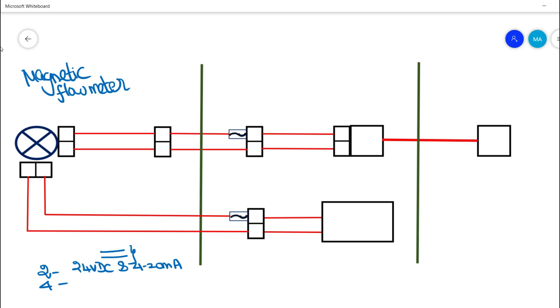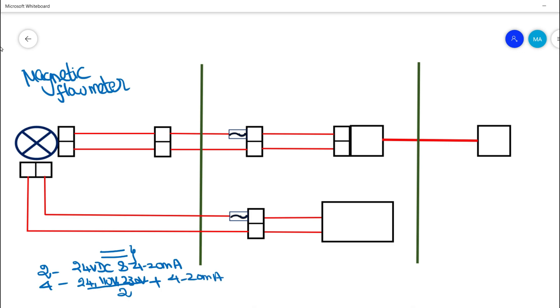In 4-wire systems we have a different power supply — it might be 24 volt, 110 volt DC, 230 volt AC, or whatever the required supply voltage — running in 2 wires. The remaining 2 wires carry the 4 to 20 milliamps signal. This is the basic difference between 2-wire and 4-wire loop systems.